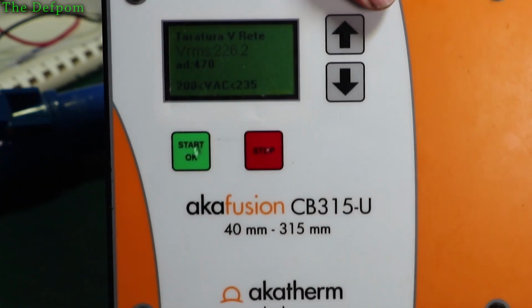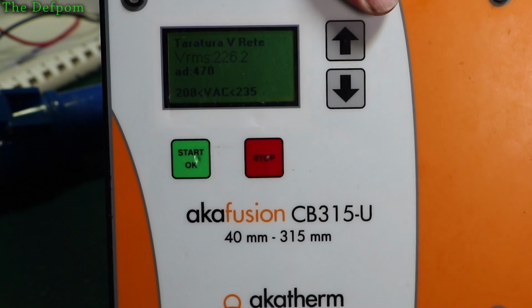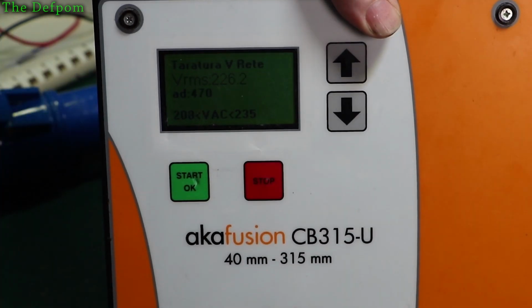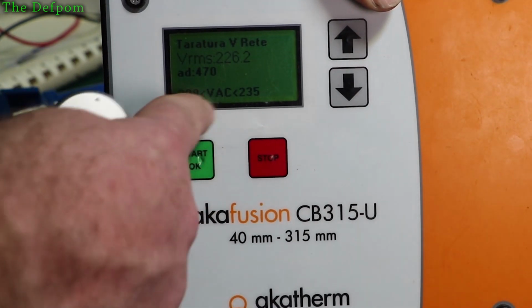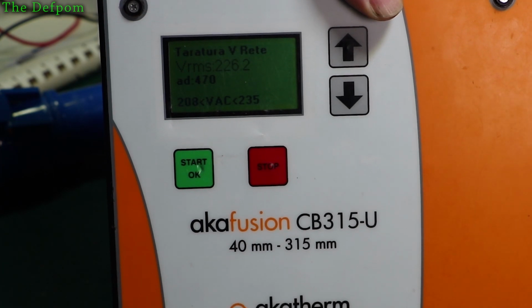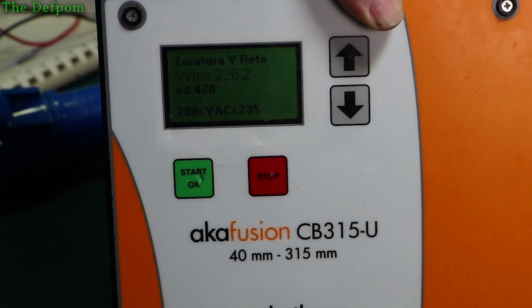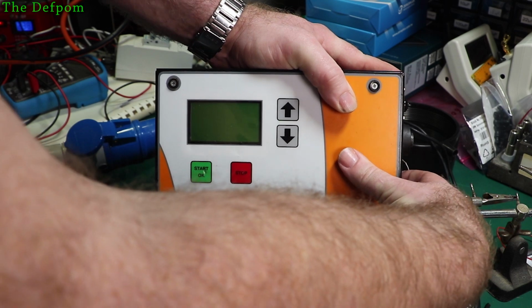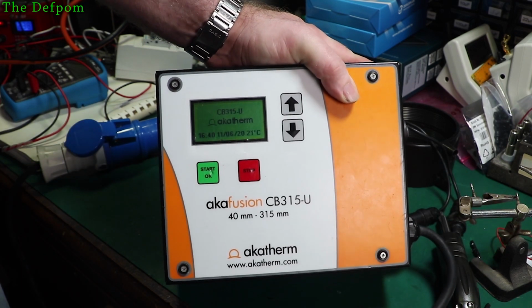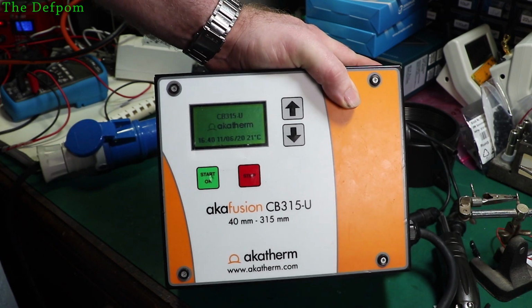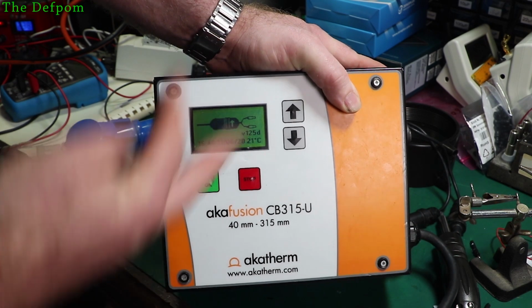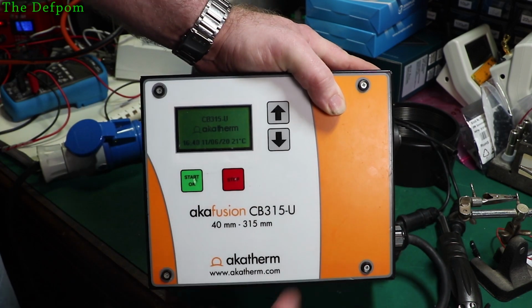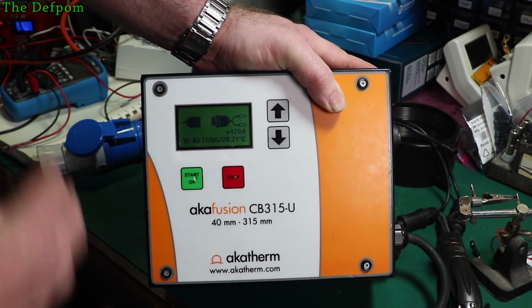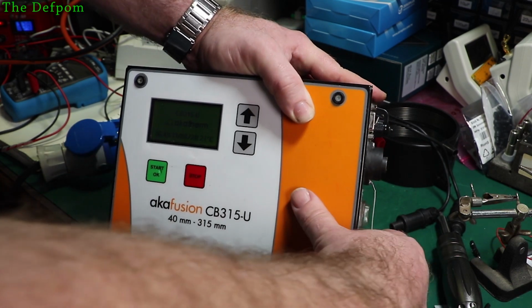So that's something to watch out for, trying to do adjustments on this in the future, that this actually reads below the actual set voltage, because it has to be within this range. You've cheated a little bit there instead of adjusting the actual tolerances. So if I turn it on now, there you go, no alarm, got the Akatherm branding back on it again, so I can change the branding. It's got a few different firms in there, so it's obviously a company makes it and then sells to a few different companies worldwide.